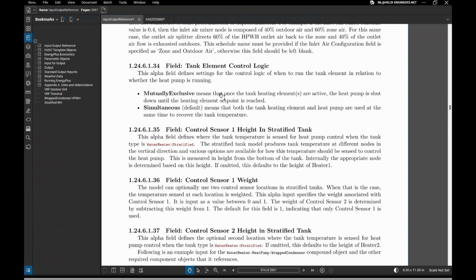The mutually exclusive option is used if the compressor is unable to provide the heating to the tank. That's when those heating elements kick on. Mutually exclusive says that if those heating elements kick on, then it locks out the compressor. Those heating elements are then used to bring the tank up to temperature, and once they have reached their set point, it allows the compressor to run again.